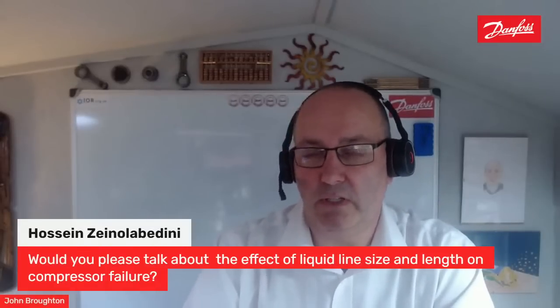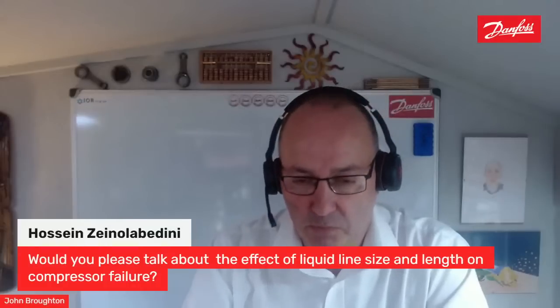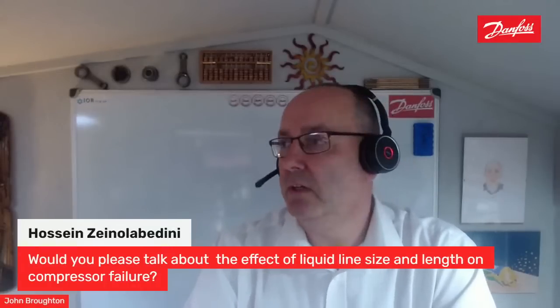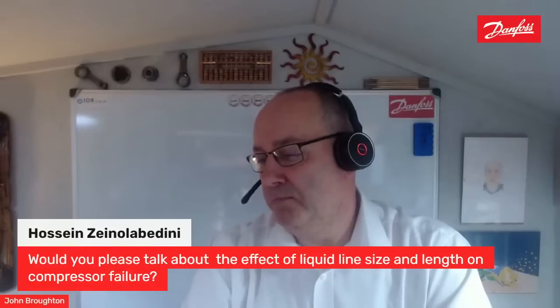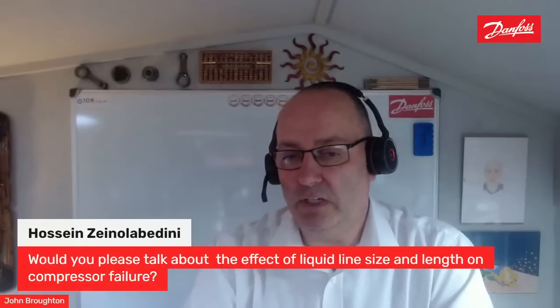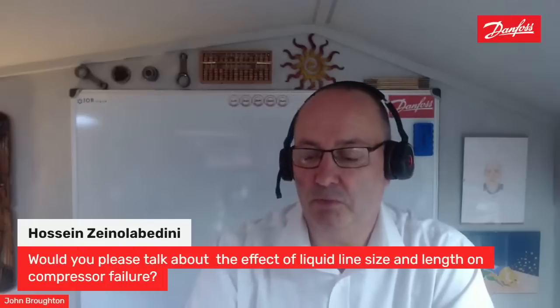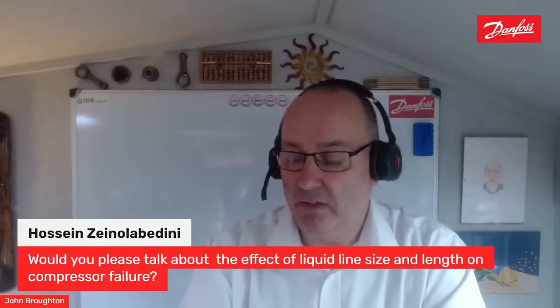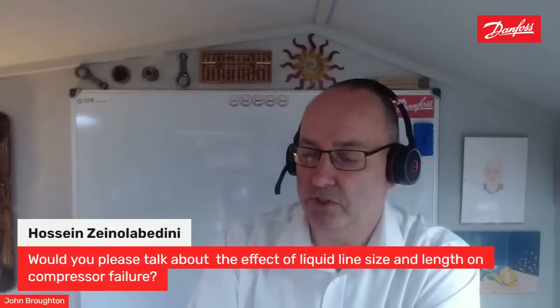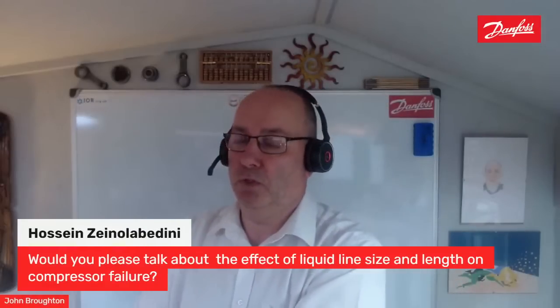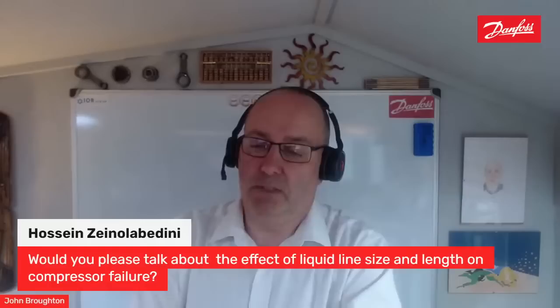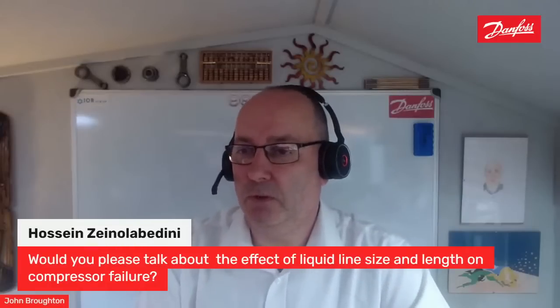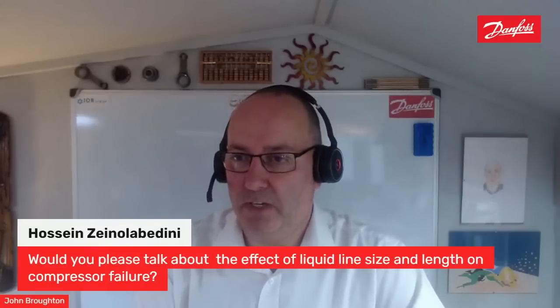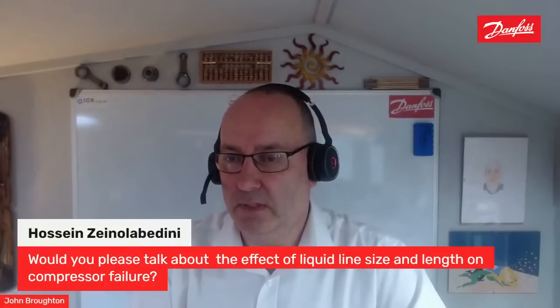So pipework generally is a huge issue for me and a challenging one when you go to site, because you'll see AC installations with 100 meters of pipework plus, and then people come onto the commercial refrigeration side and do exactly the same thing and then wonder why the compressor fails. So that really is important to me. So I hope that answers that correctly, Hossein. If it does, give us a thumbs up.